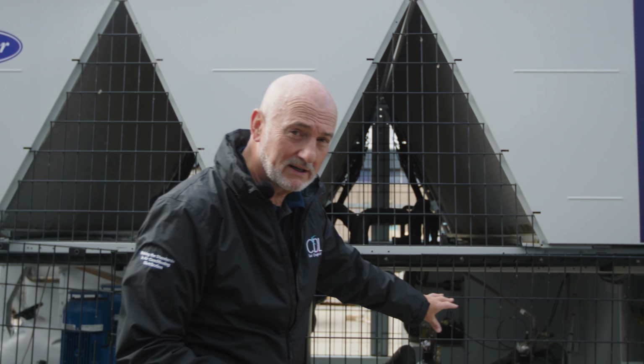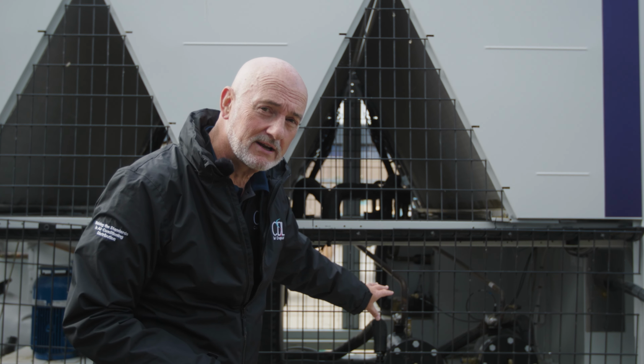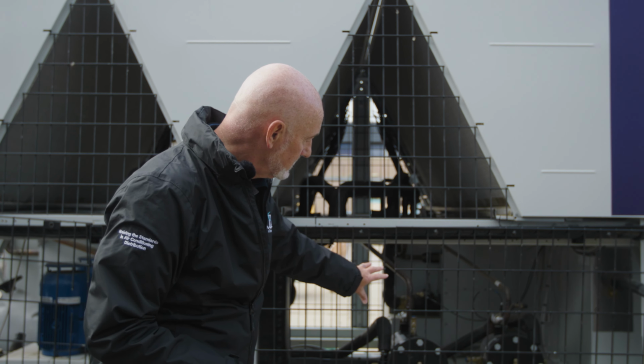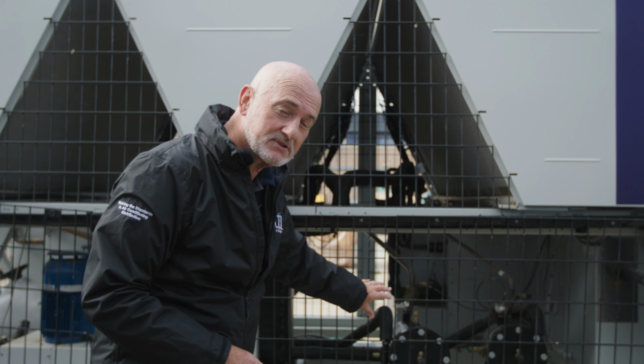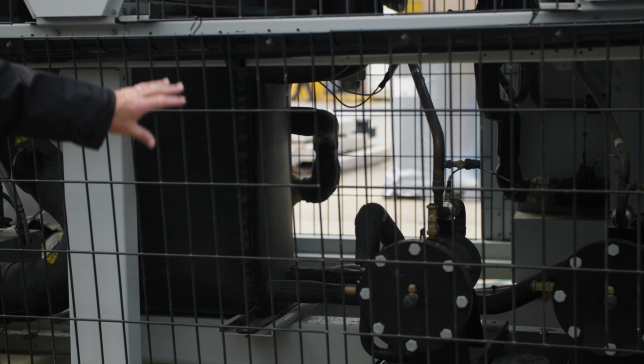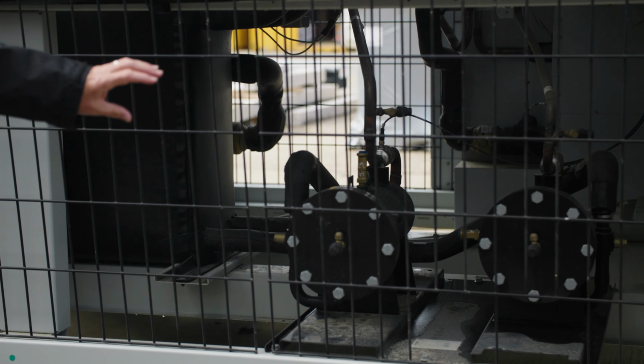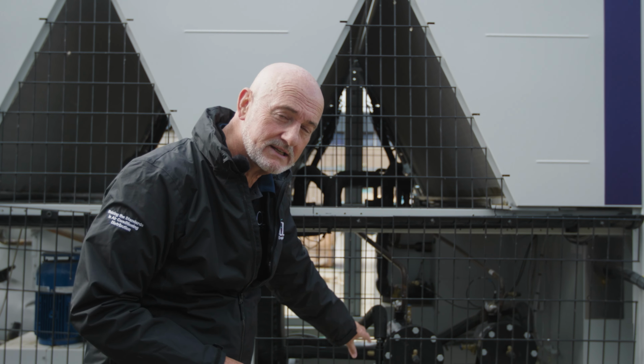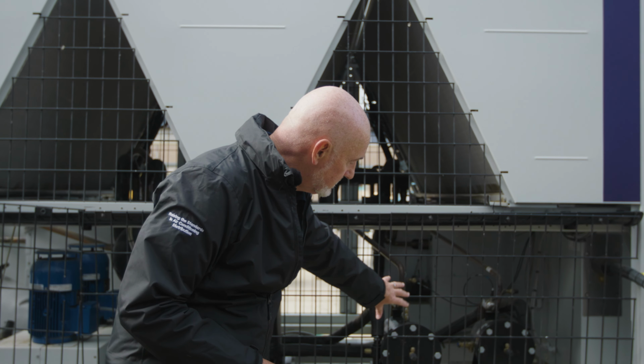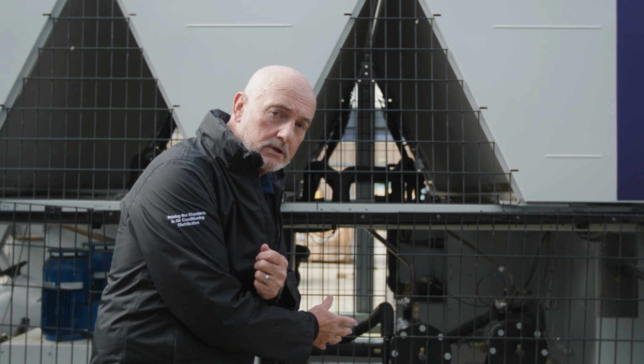So another component, it's not one of the major components, the major 4 components being a condenser, evaporator, an expansion device and a compressor. But an important item, quite large on this particular machine, is the filter dryer on the refrigerant side. This filter dryer is on the liquid and it keeps the internal refrigeration circuit, which is quite chunky on this machine, and it just keeps it clean. And these are called replaceable core dryers. You just take the end off, replace it with a new core and pop it in.